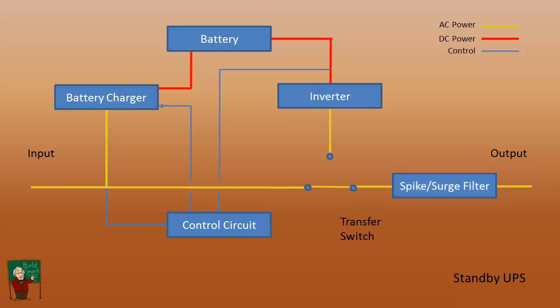It will look at the incoming line voltage, and if that voltage is out of specification for what it's supposed to be, it can activate the inverter, and also has a connection to the transfer switch, so it can transfer over to battery power. There'll be an alarm circuit, and this will be designed to tell you if something's out of whack with the system. So I'm powering this up. We'll see that we end up with power to the battery charger and going through the filter at the end and to the output. We have an alarm set right here, and it's because the battery is discharged. It needs to charge up. So we're showing a discharged battery alarm.